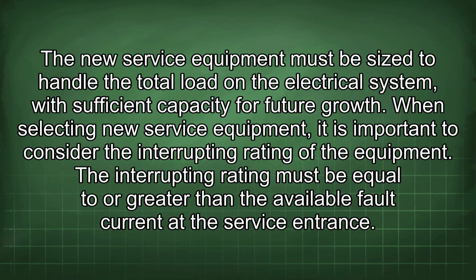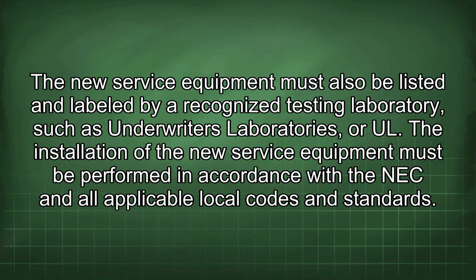The new service equipment must be sized to handle the total load on the electrical system with sufficient capacity for future growth. When selecting new service equipment, it is important to consider the interrupting rating of the equipment. The interrupting rating must be equal to or greater than the available fault current at the service entrance. The new service equipment must also be listed and labeled by a recognized testing laboratory, such as Underwriters Laboratories, or UL. The installation of the new service equipment must be performed in accordance with the NEC and all applicable local codes and standards.